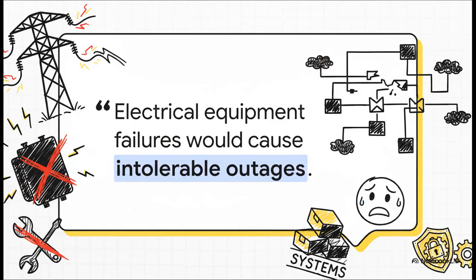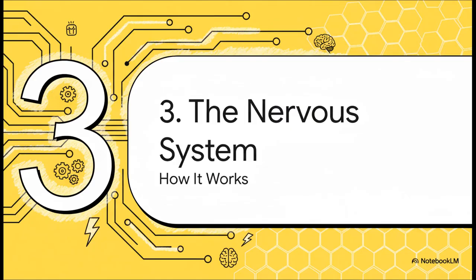And this really gets to the core reason this technology exists. As our source, the art and science of protective relaying, puts it, just hoping that equipment will never fail is a recipe for absolute disaster. Designing a system just for normal operation would lead to, and I'm quoting here, intolerable outages. You have to plan for failure. And this is where all that planning really pays off. The solution is this incredibly elegant system that acts just like the grid's own central nervous system.